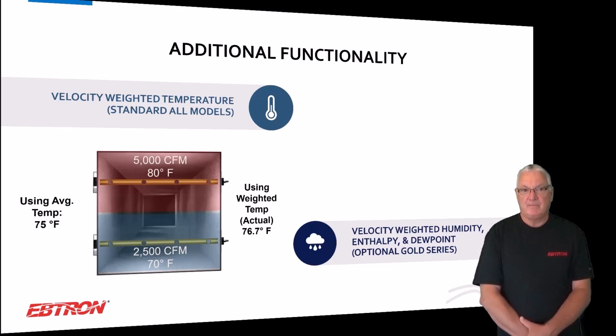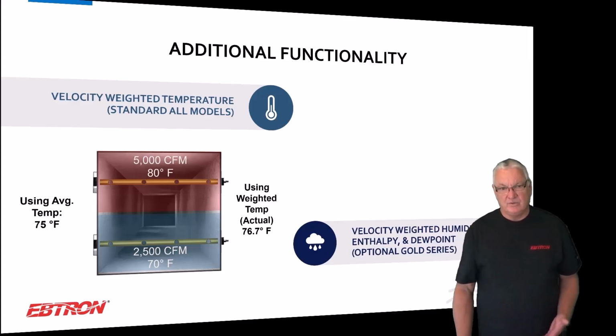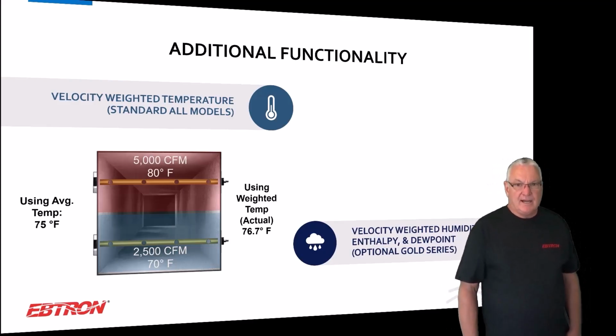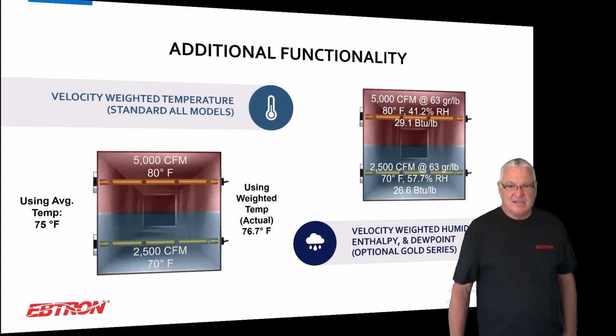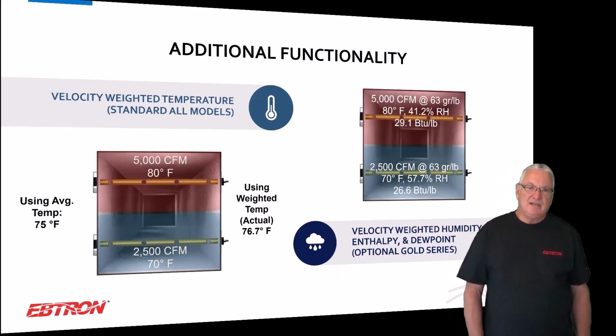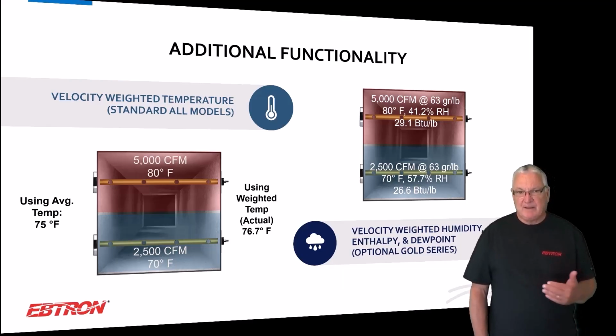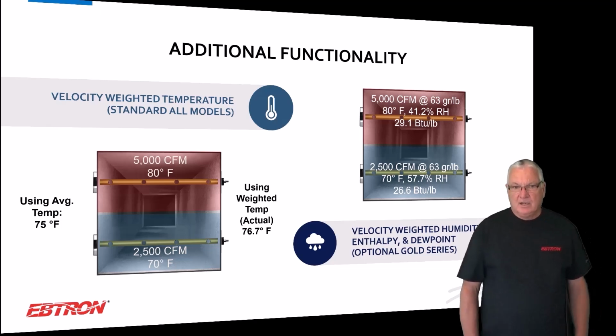And I tell people all the time that use this stuff, there's a lot of applications for where you need good temperature measurement. Use this device. It's a great device on your outside air for making a decision for those of you that do dry bulb switchover. And then on the other side of it, we added a humidity sensor, and it's the same deal here. I mean, we've got, I'll use the same temperature profile, but now when you look at this, and again, it's another tough little thing to see on a webinar.